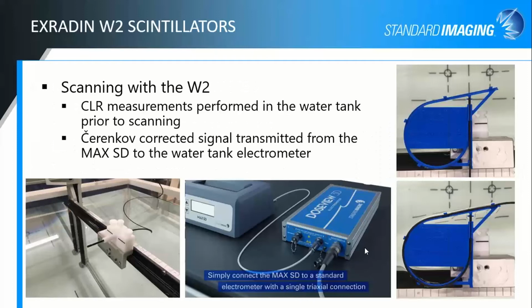So if we look at a little bit of that setup, I have probably better pictures here. I guess it's the same for the Max. If you would want to do your CLR measurements sometime prior to scanning, it doesn't have to be day of. It holds for a while. It's pretty stable. But you would have that minimum fiber configuration, maximum fiber configuration. And then for scanning, there's actually an adapter sleeve that lets it fit any chamber holder. This is our Dose V3D tank, but any chamber holder that will hold a scanning chamber with either a 7 millimeter or an 8 millimeter diameter stem. So you can use it with any other water tank, not just ours.